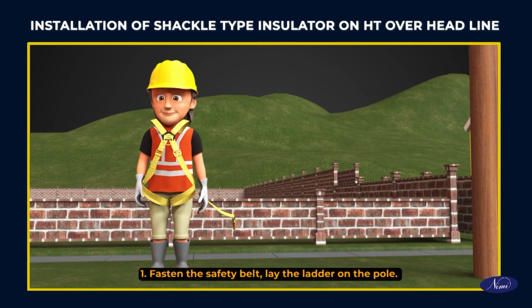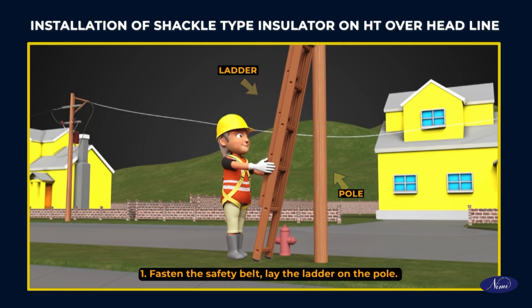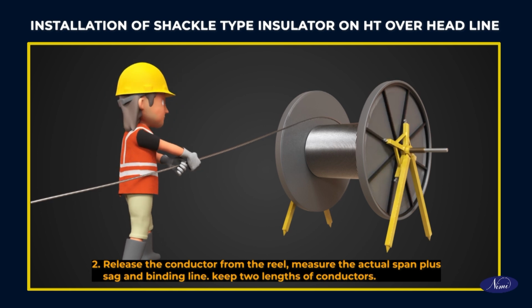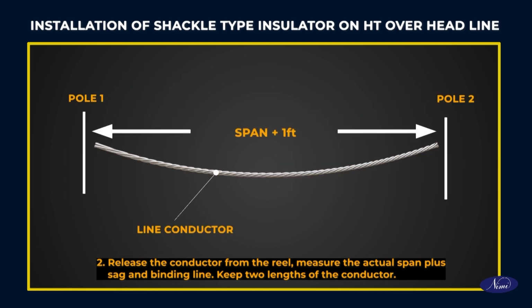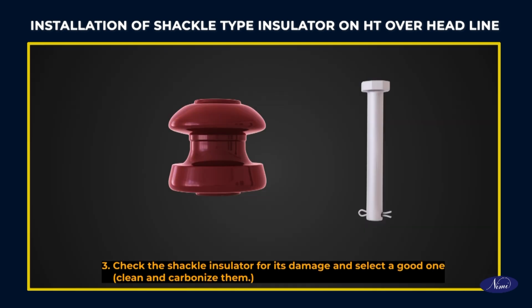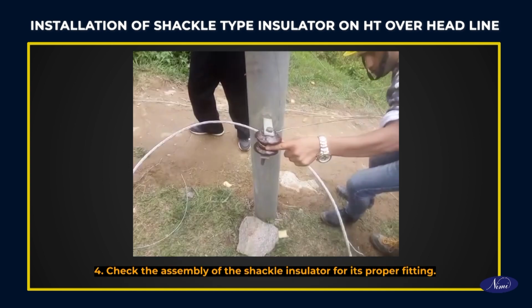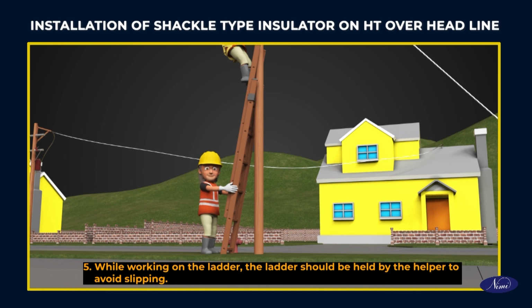Fasten the safety belt, lay the ladder on the pole. Release the conductor from the reel, measure the actual span plus sag and binding line. Keep 2 lengths of the conductor. Check the shackle insulator for its damage and select a good one. Check the assembly of the shackle insulator for its proper fitting. While working, the ladder should be held by the helper to avoid slipping.